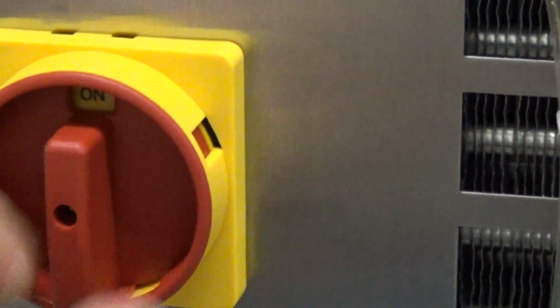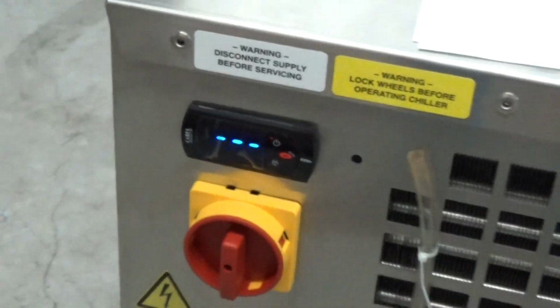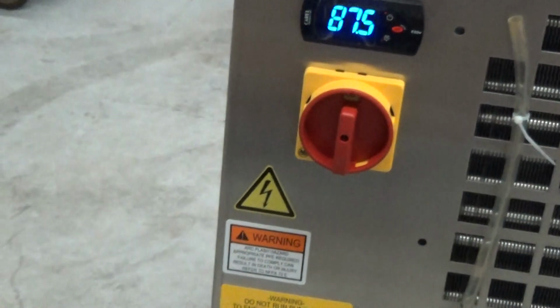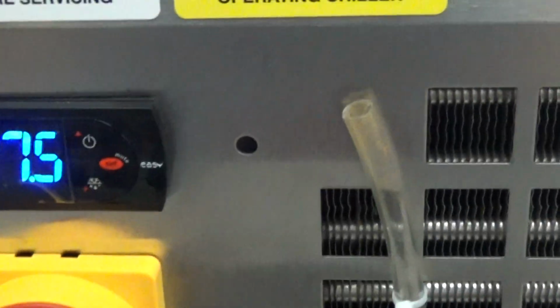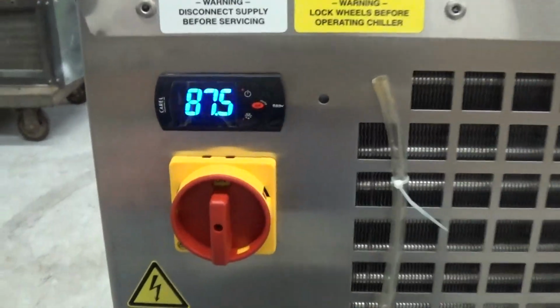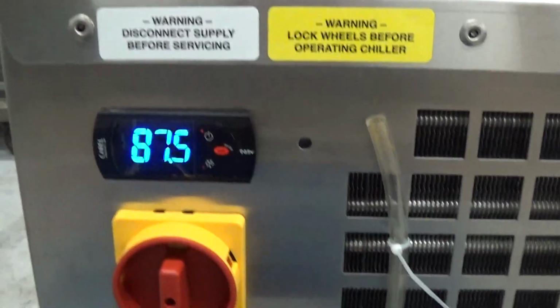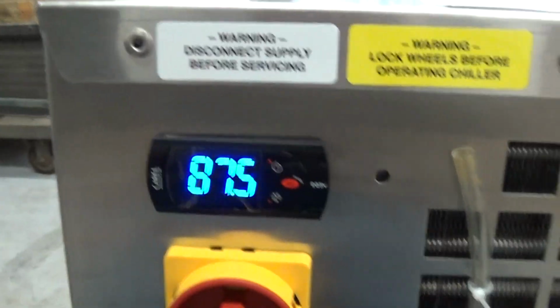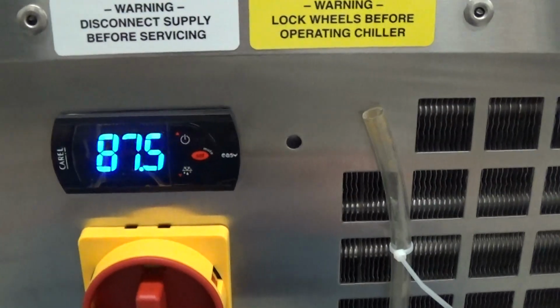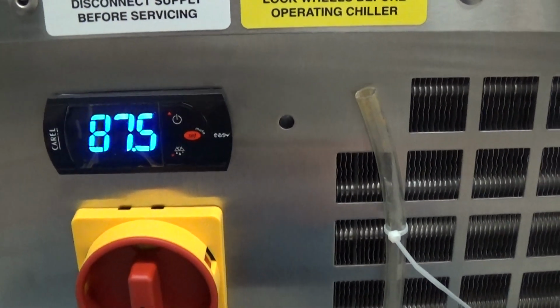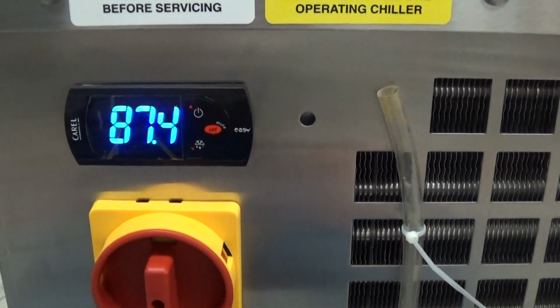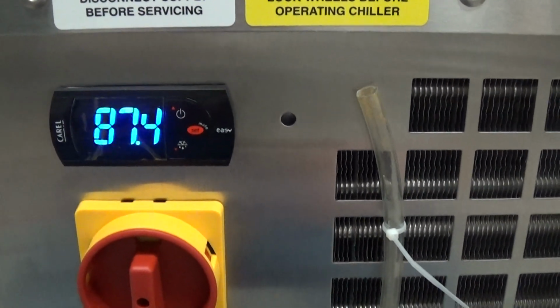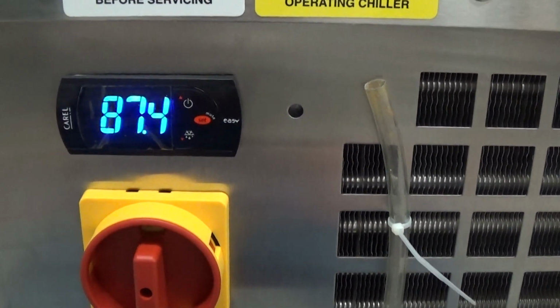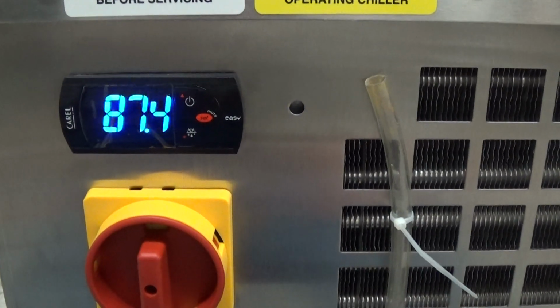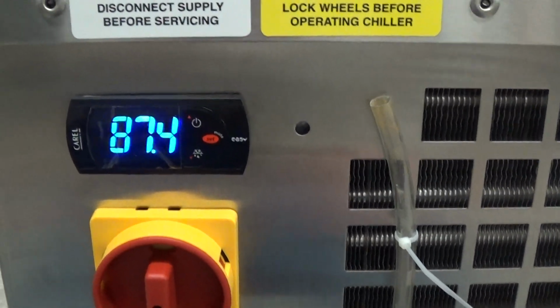We're going to go ahead and turn the unit power on here. And after we start chilling, I'll show you the insides of the unit. We've just been running it for a while. Just the heat from the pump alone can help get the fluid that's in that little reservoir tank up to a temperature we can test at. The range of this unit is 50 degrees Fahrenheit to 90 degrees Fahrenheit.